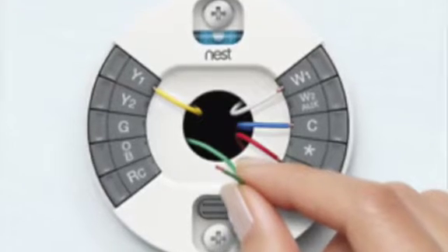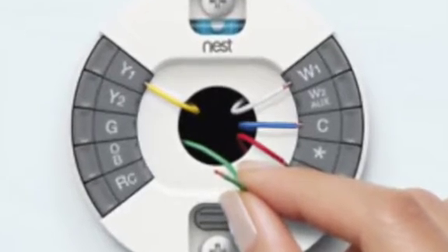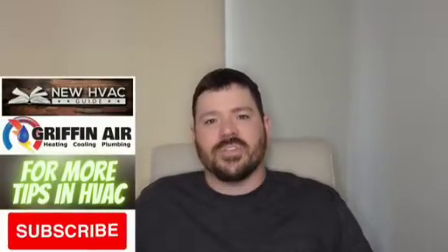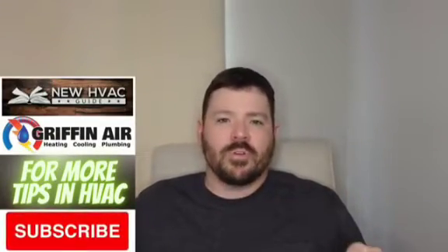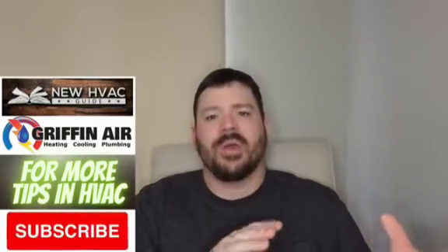But what I would say in most cases, if you do have pinch tabs, when you stick that wire up in there, kind of pull out on that tab a little bit. You don't have to be a He-Man about it, but just pulling out on it a little bit, making sure that it's pinching, it's making a good connection, and you should have less issues. It's not a big common thing, but there are times when folks will install those pinch tab type and have issues because it's not making a good connection.